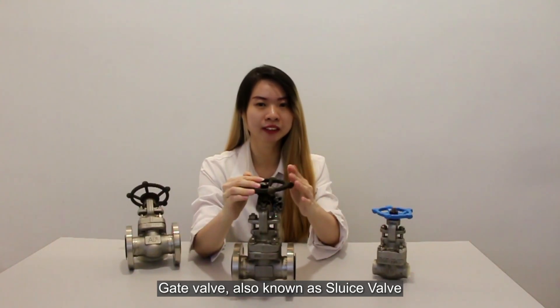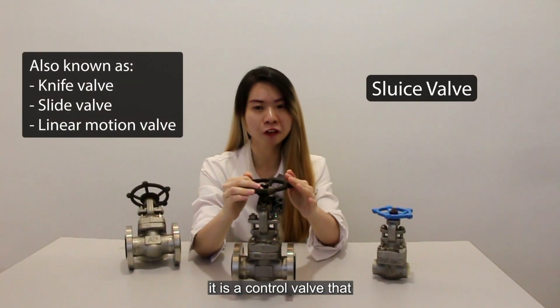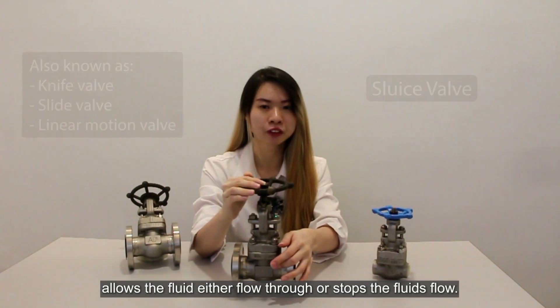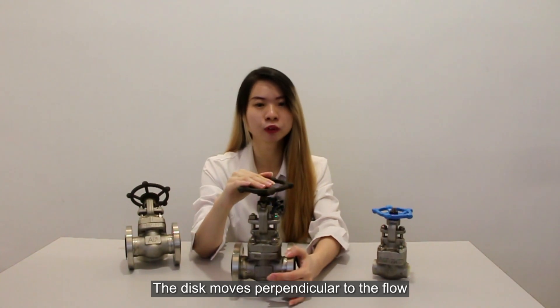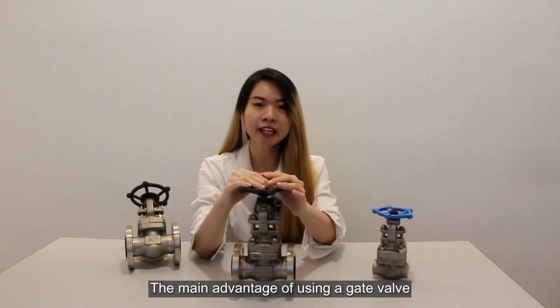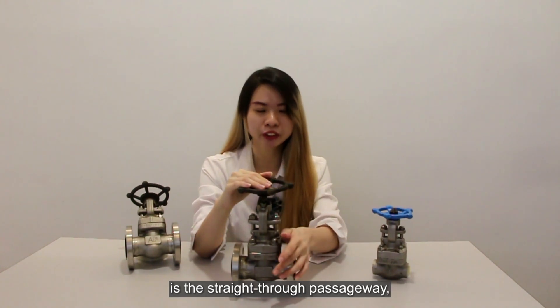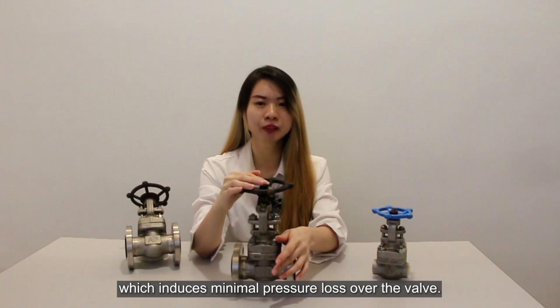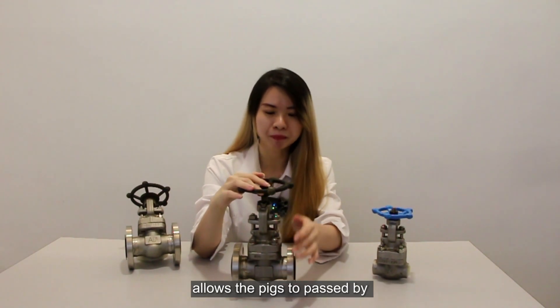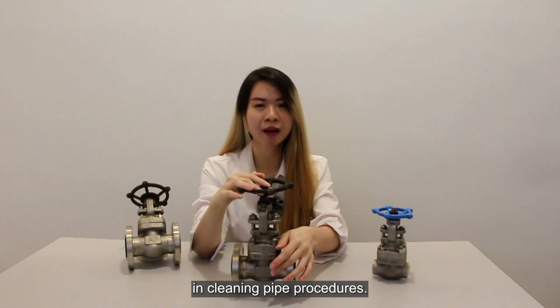Gate valve, also known as sluice valve, is a control valve that allows the fluid to either flow through or stop the fluid flow. It is used to move the disc perpendicular to the flow when the fluid is shut off or stopped in the piping system. The main advantage of using the gate valve is the straight-through passageway, which induces minimal pressure loss over the valve. The full bore design of the gate valve allows a pig to pass by in the cleaning pipe procedure.